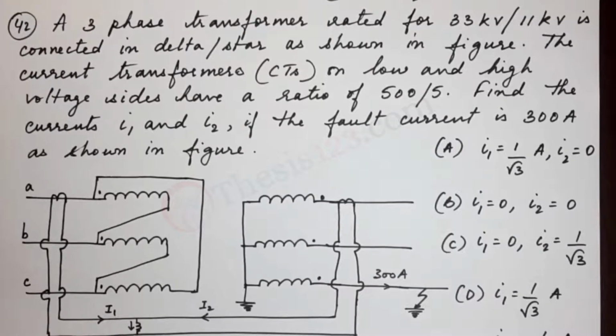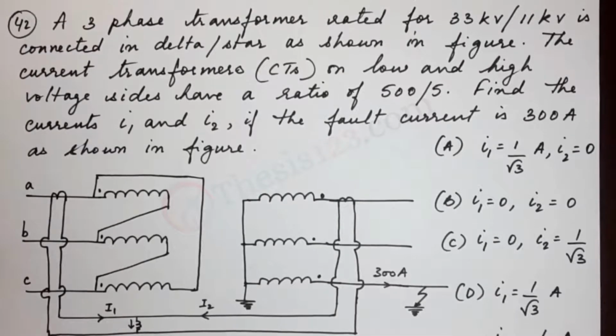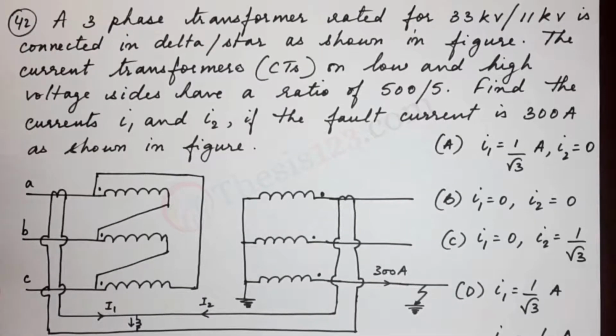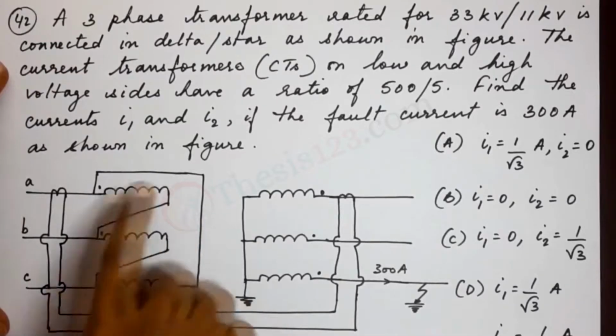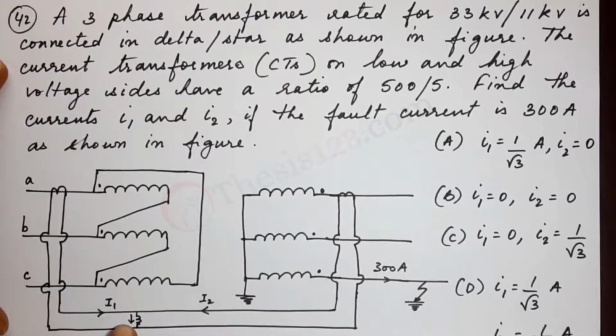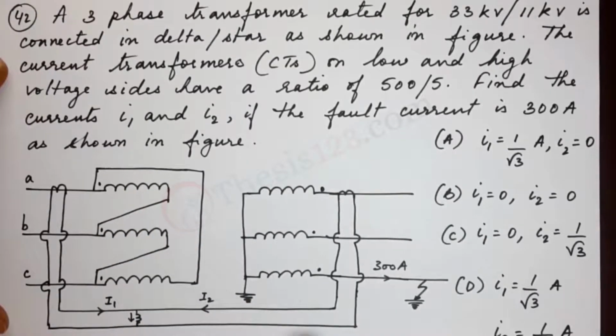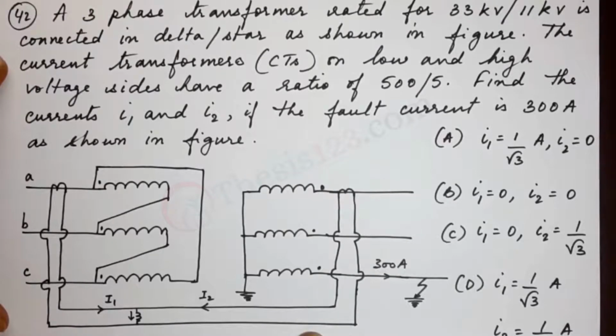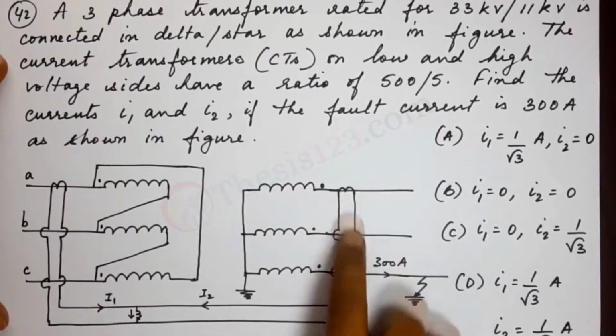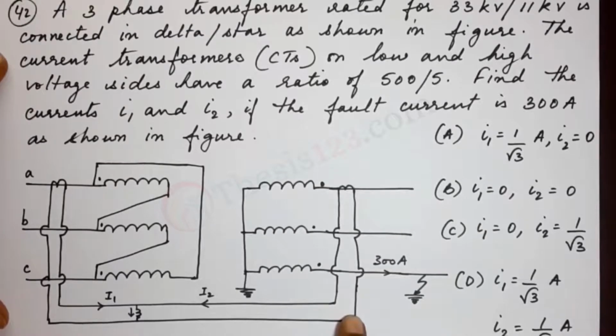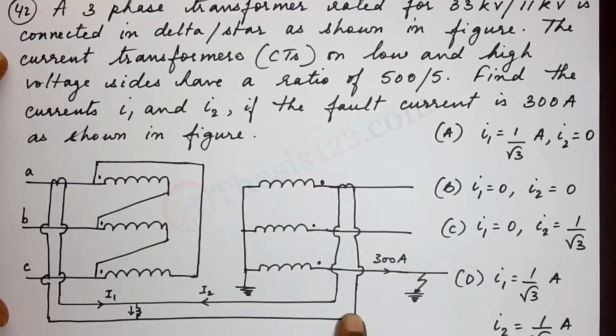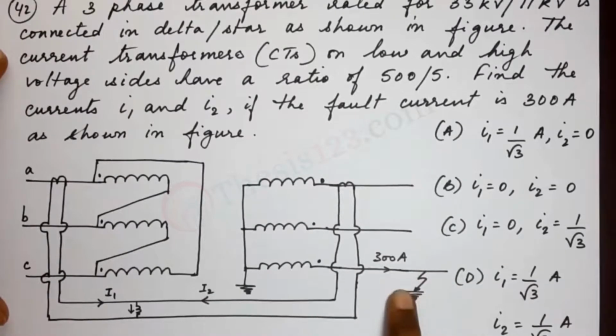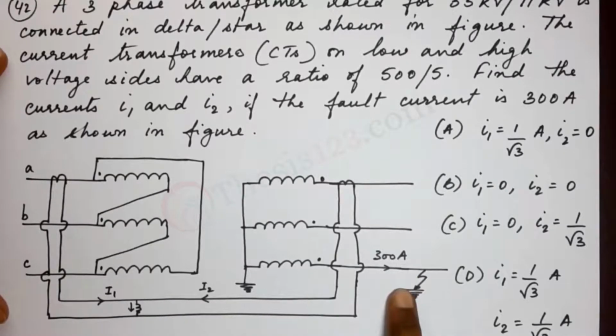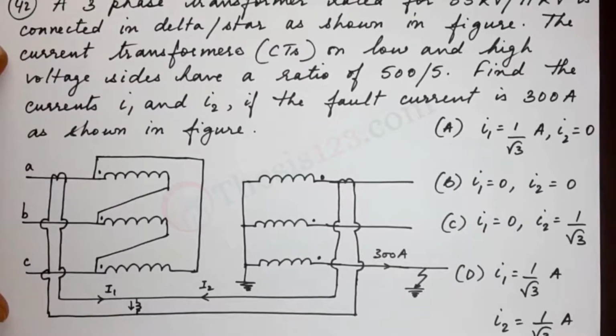Now if you look at the figure here, we see that the transformer is connected in delta to star connection, delta to star connection shown over here. Now the current transformers are connected and they have a certain ratio of 500 to 5, and the fault current here is 300 amps. That's what's given to us.